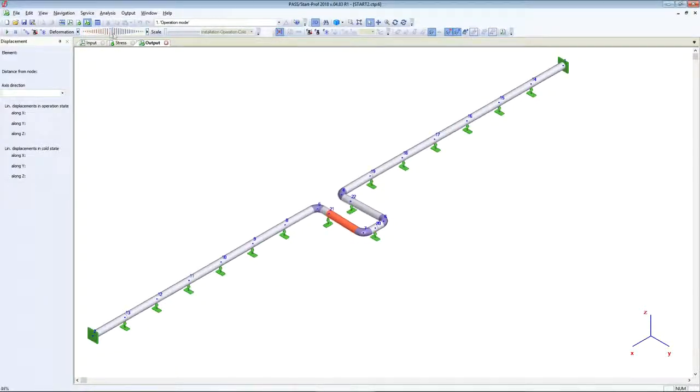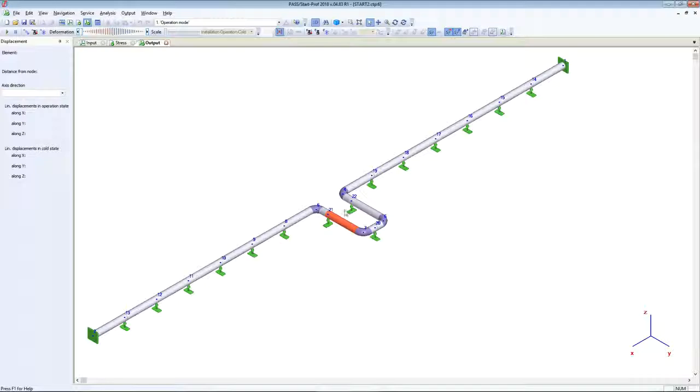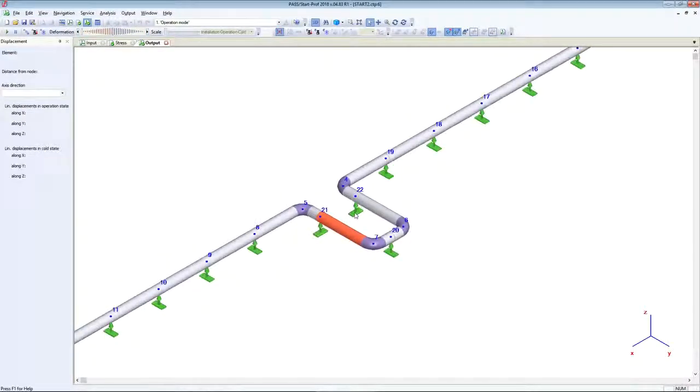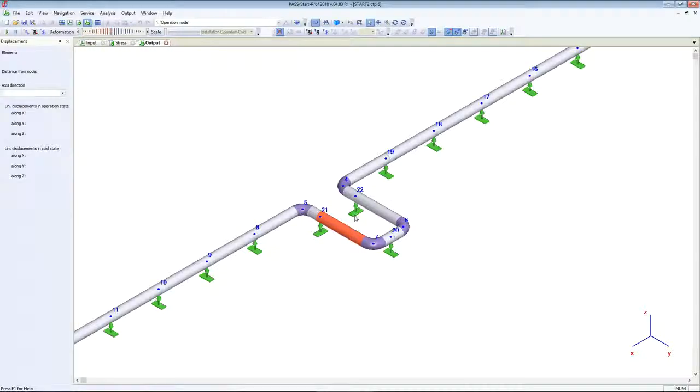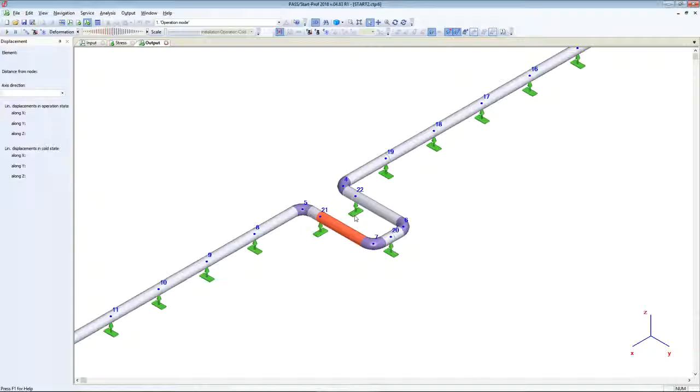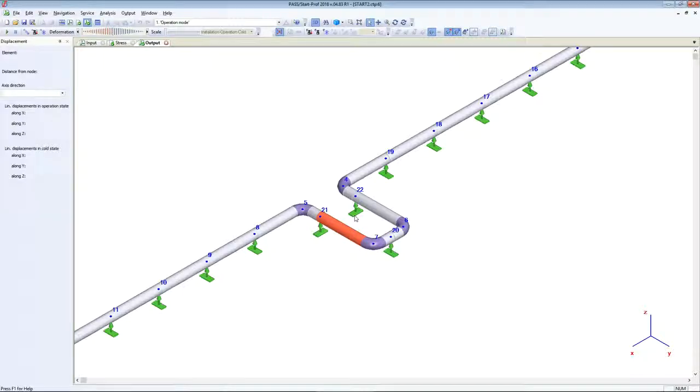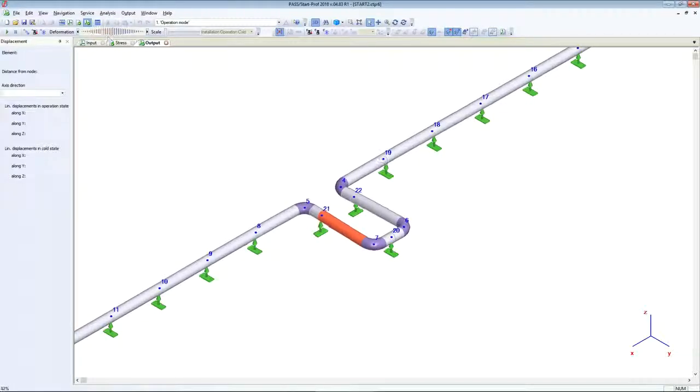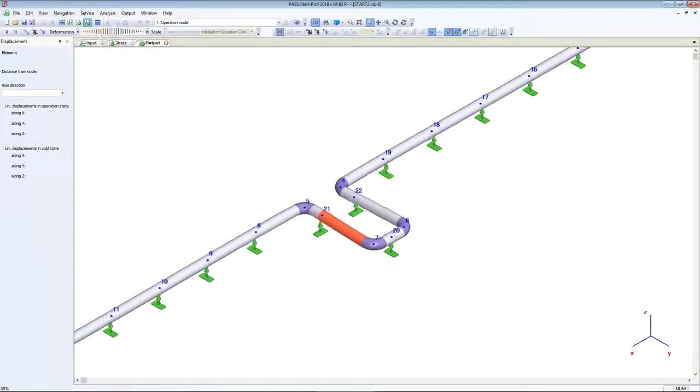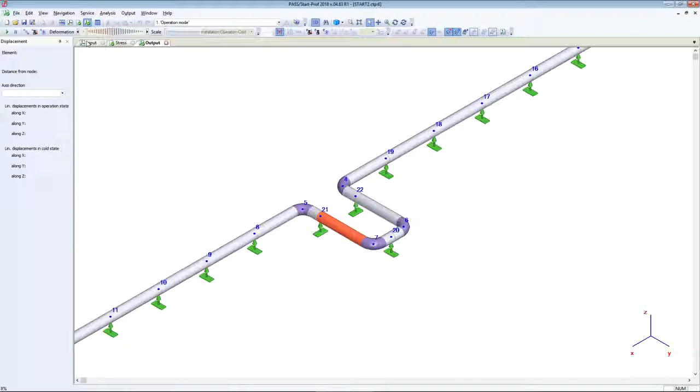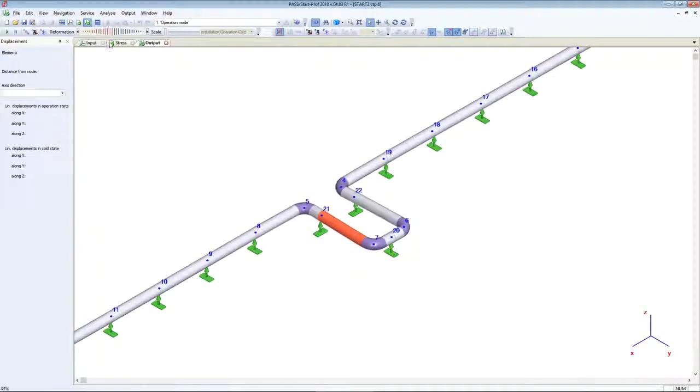The main problem with plastic piping is that temperature expansion is very huge - it's about 10 times greater than for steel piping. So the temperature difference of 42 degrees is like 400 degrees for steel piping. For steel piping you will not see anything because the deformations are very small, but here we can see how our piping expands under temperature.